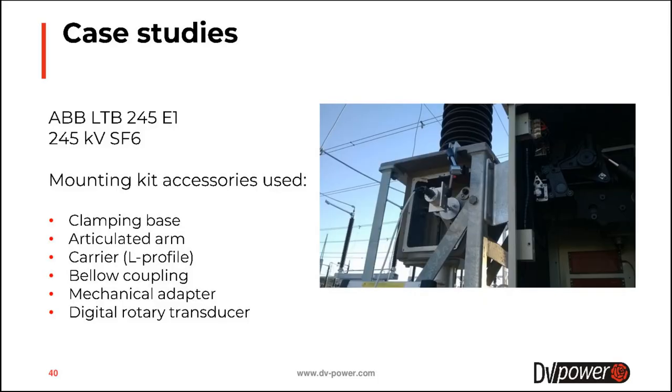Okay, these types of live tank circuit breakers almost always have a convenient place for rotary transducer mounting. The ABB LTB type of circuit breaker is exactly a live tank, and in this case a rotary transducer is mounted in the center of the rotating shaft, which transmits mechanical energy from the operating mechanism to the rod of the main contacts.